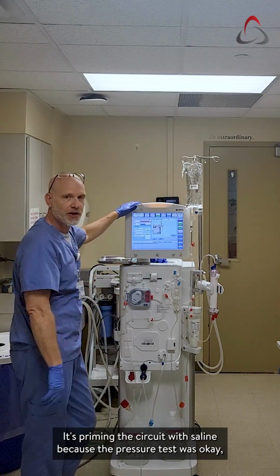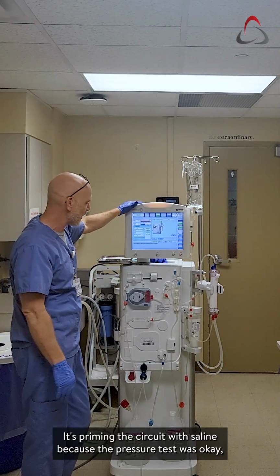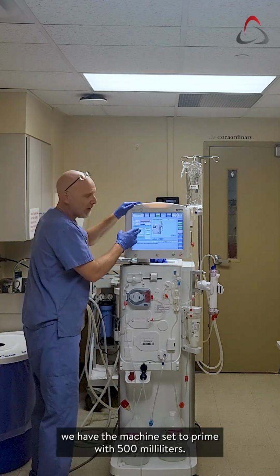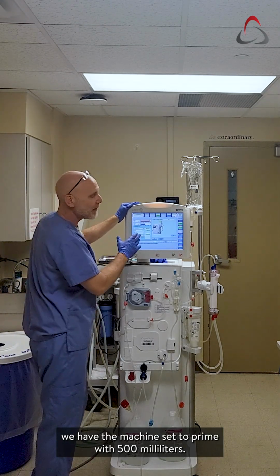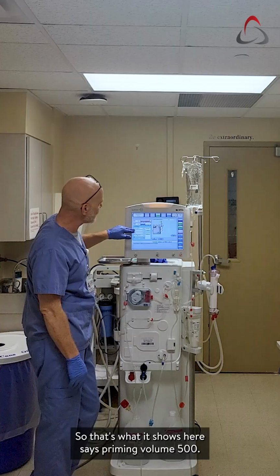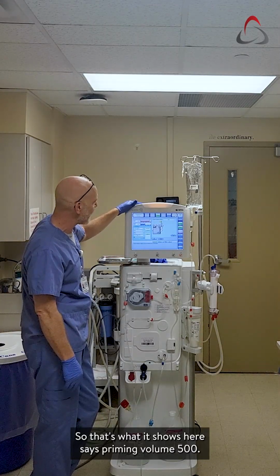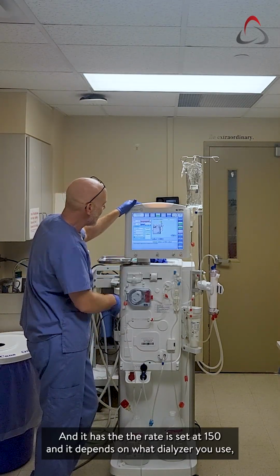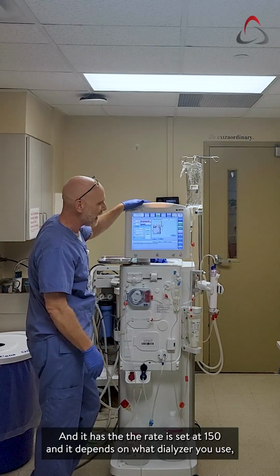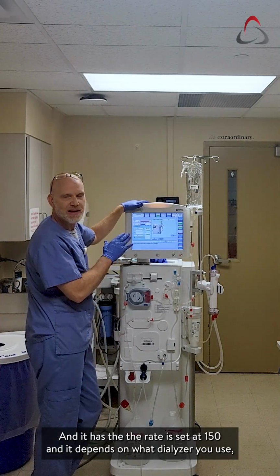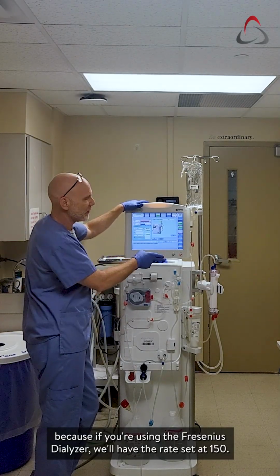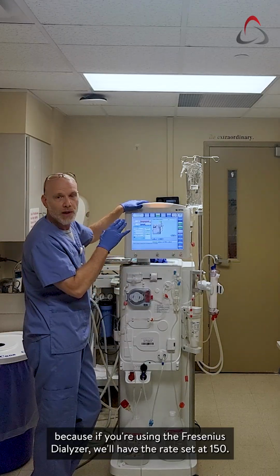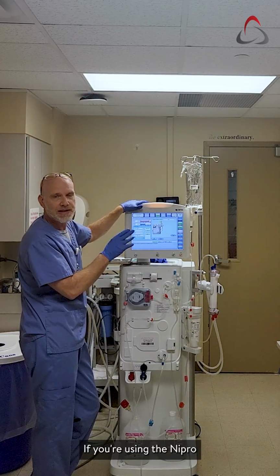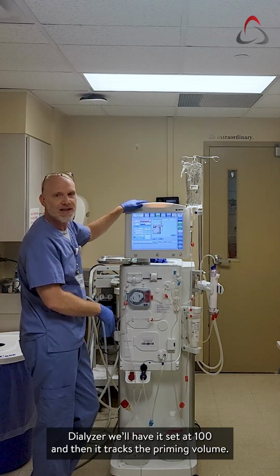So the blood pump segment starts. Now it's priming the circuit with saline because the pressure test was okay. We have the machine set to prime with 500 milliliters. So that's what it shows here. It says priming volume 500, and the rate is set at 150, and it depends on what dialyzers you use, because if you're using the Fresenius dialyzers, we'll have the rate set at 150. If you're using the Nipro dialyzers, we'll have it set at 100.